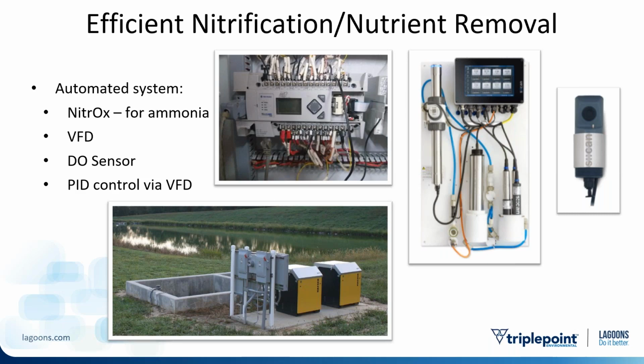What you do is set up the ladder logic and the PID control of that blower through a VFD such that you're reading your dissolved oxygen, and you're reading your dissolved oxygen in the effluent.